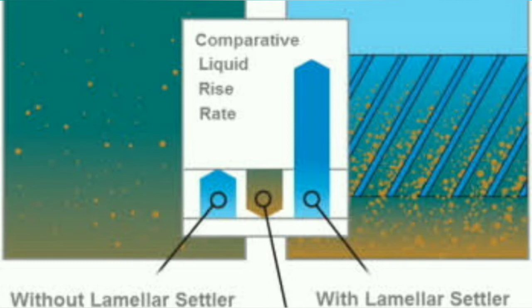Clarifiers equipped with tube settlers can operate at two to four times the normal settling rate, and it is possible to cut coagulant dosage by up to half while maintaining lower turbidity. Tube settlers reduce the required area for a sedimentation tank, reduce coagulant dosage, and allow existing sedimentation systems to be retrofitted and converted. They also require less filter backwashing, reducing load on downstream filters, and increase allowable flow capacity by expanding settling capacity and improving solid removal.